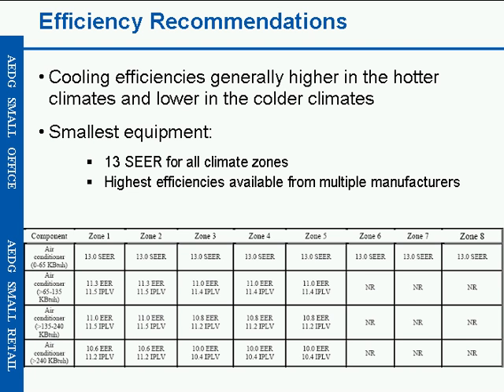Here's an example of the cooling efficiencies that are contained in the guide. You'll see the range of sizes of rooftops or split systems for the air conditioners based on SEER or EER from climate zone 1 through climate zone 8. This table shows the range and how the recommendations vary over the climate zones. In general, the cooling efficiencies were higher in the hotter climate zones and lower in the colder climate zones.